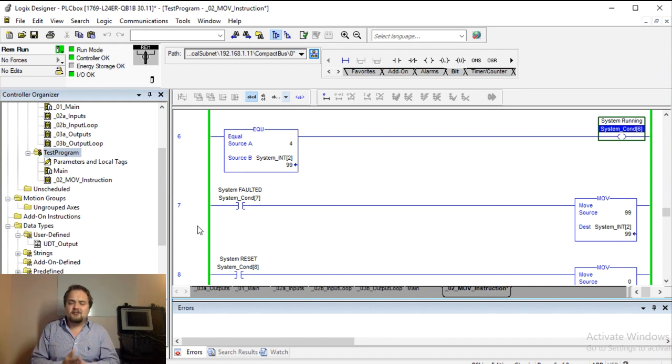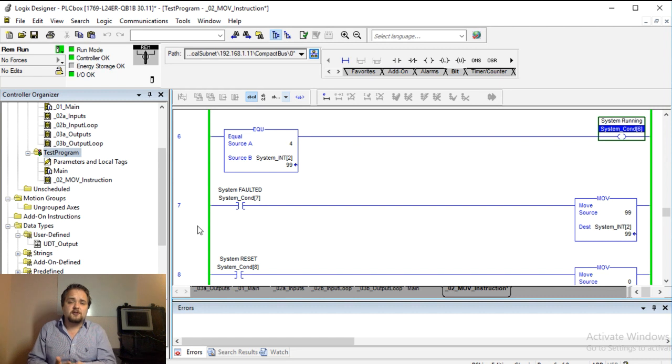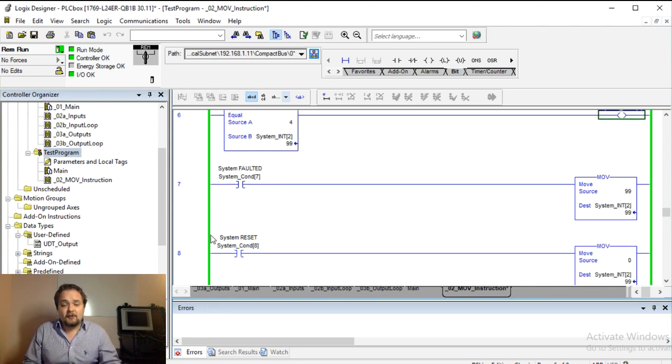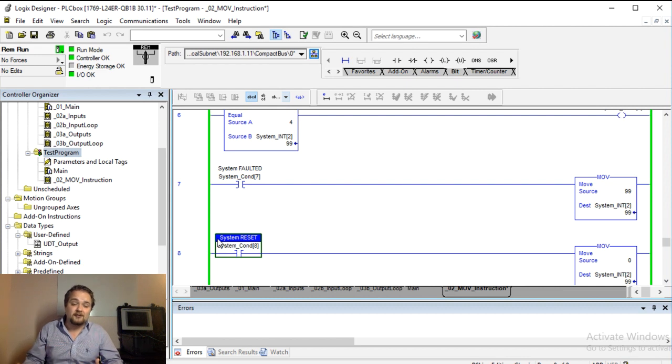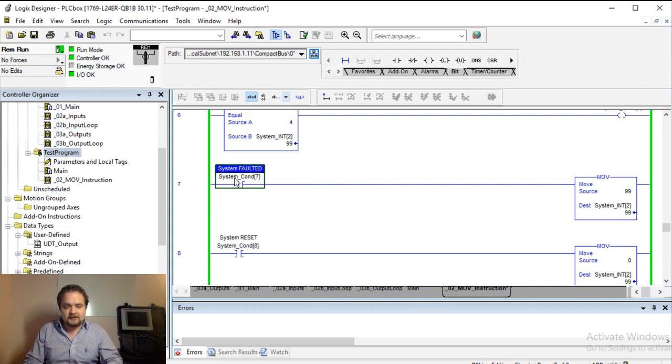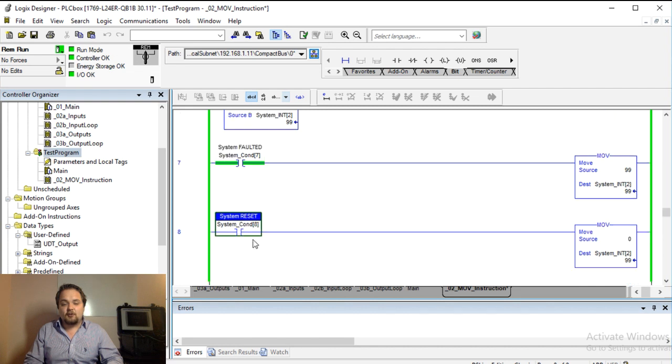And at this point if it's equal to 99 you can of course implement stop routines for your motors, you can de-energize your safety circuit, you can drop out air, so on and so forth. In order to reset the system you'll have a push button. So of course if the faults are clear, if this fault bit is, if it's of course energized then there's no point in pressing this reset.